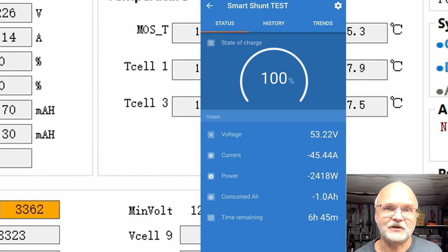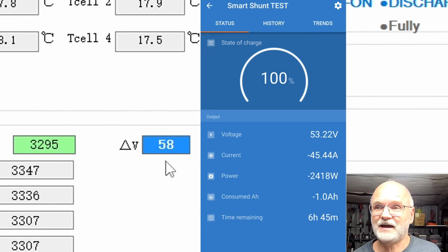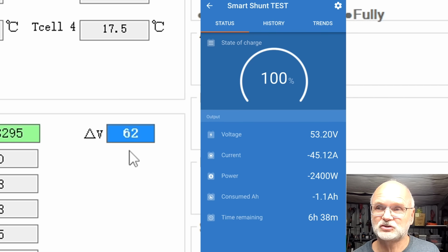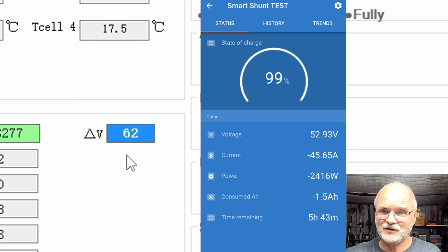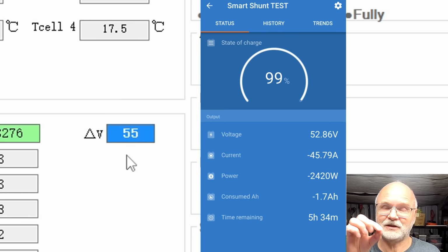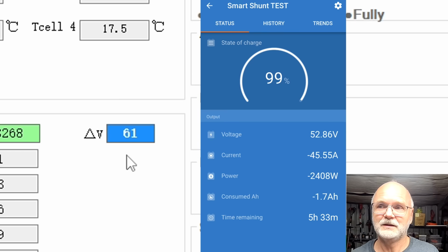And here people are always interested how the deviation looks like when the battery is full and gets discharged. So you can see the deviation going up and down a bit because we are using an inverter, and the inverter is not a constant load for the battery, because it replicates the sine wave of our AC output. Depending at what point the BMS measures the DC current, it could be very high or very low, so that's why we see the voltage going up and down as well.